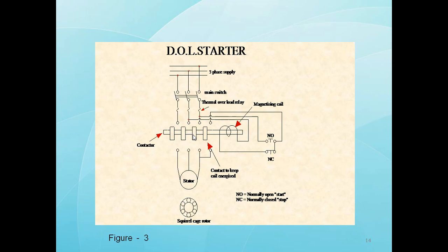In case of overload on the motor, the contacts of the overload relay will open and subsequently the motor stops. The fuses are provided for short circuit protection.